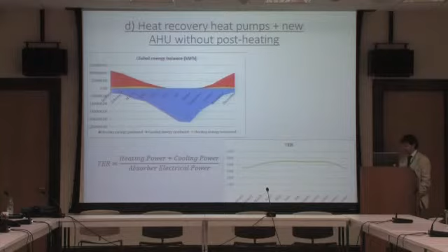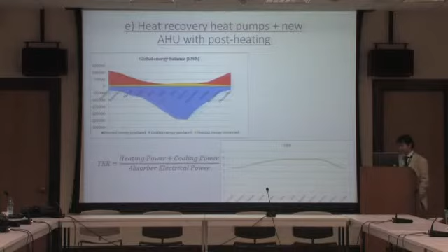And then the combination of the air handling unit and the heat recovery heat pump. Here you may see that for the post heating, you always recover the whole heat. So the post heating is for free. You will have to condense a little bit higher compared to the outside temperature. In any case, you can recover the whole heat where possible. You can really control the relative humidity inside the building better.